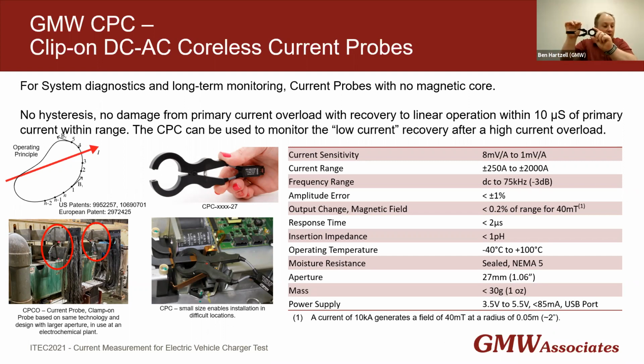It's easy to secure. Well, you can't really see against the background, but I have a couple of cable ties. Easy to secure with, say, a cable tie, compared to having to mount a heavier measurement device. The package is sealed, moisture resistant, with a temperature range of minus 40 degrees Celsius to 100 degrees Celsius, suitable for harsh environments. These are commonly used in test cell chambers with moisture and large temperature cycles, with repeated frost and thaw cycles.